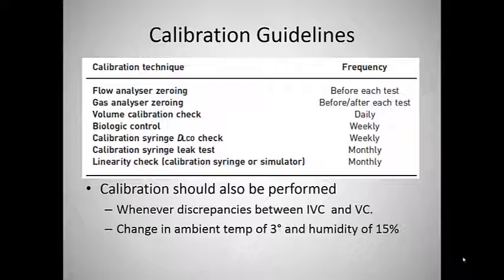They should be documented in the laboratory. We keep a notebook of this. They have to keep track of this. They have to date it. They have to time it. And I do check these periodically. If you ever want to see how it's set up, again, you guys set up your own labs. These are requirements. JCAHO often skips over these things because they don't understand it themselves, but every now and then you get a sharp person that comes in and knows about this, and he will ask for your logbooks and stuff to look at those.